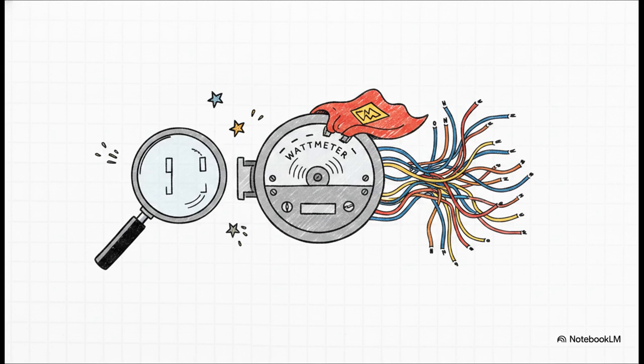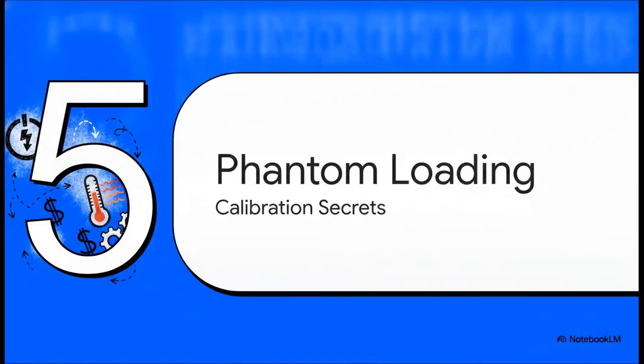By leaving them unlinked, you can actually isolate the current coil to run what's called a creeping test. That's where you check if the meter's disk is falsely rotating just from the voltage field alone, even when absolutely zero power is being drawn. Plus, separating them unlocks some highly specialized setups, like measuring reactive power across complex three-phase loads, which requires tapping into completely different voltage lines. Which leads perfectly into Section 5, phantom loading and calibration.